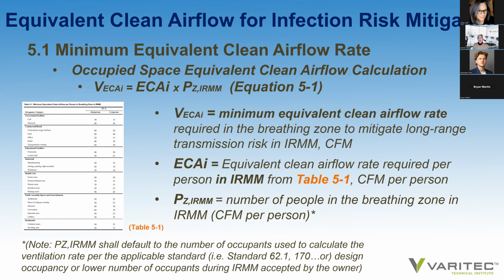Well, how do you calculate the equivalent clean airflow rate to the environment, to a zone? Well, first of all, ASHRAE Table 5-1 in the 241 standard provides the prescriptive equivalent clean airflow rate at the breathing zone when a building has been assigned to go into infection risk management mode. They're going to increase the equivalent clean airflow rate at the breathing zone. So to do that, you determine how much equivalent clean airflow is required per zone times the number of occupants in each zone.